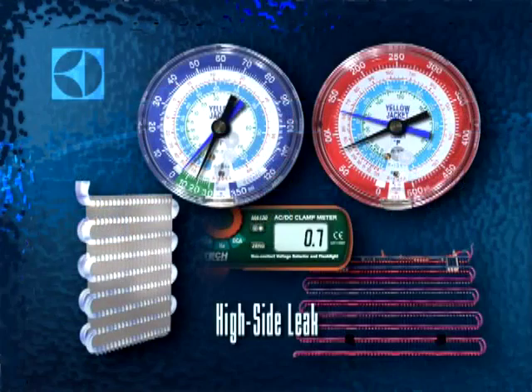High side leaks will feature low readings on both the low side and high side, with a low electrical reading. The evaporator may be only partially frosted or not frosted at all. You should hear some hissing and gurgling at the inlet. And you should find the condenser slightly cooler than normal from lack of pressure. Also, the compressor will run very cool and quiet.